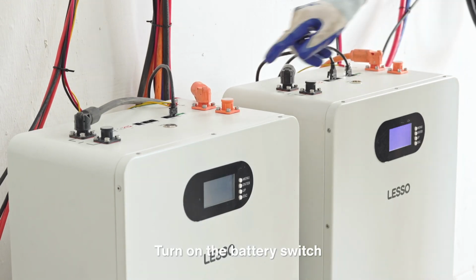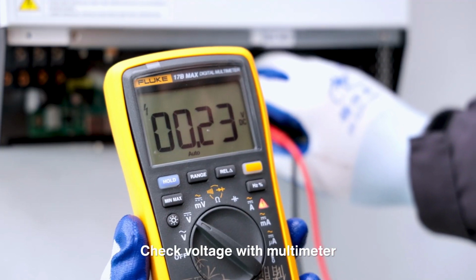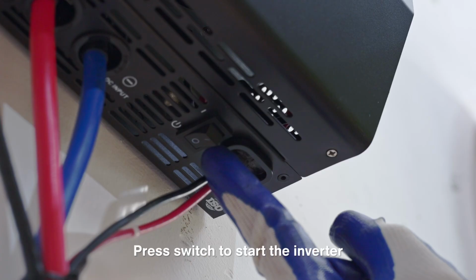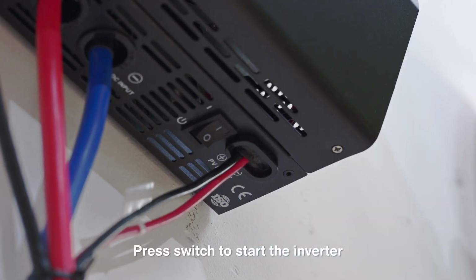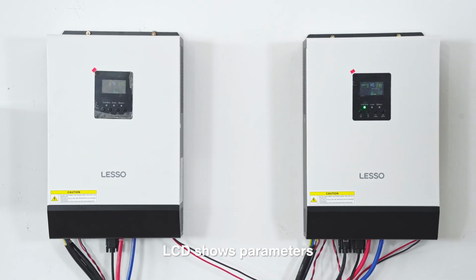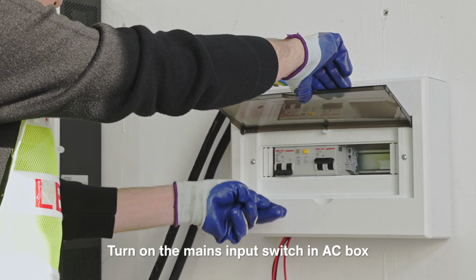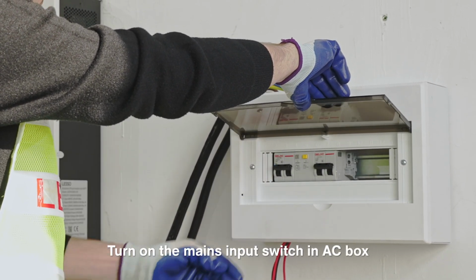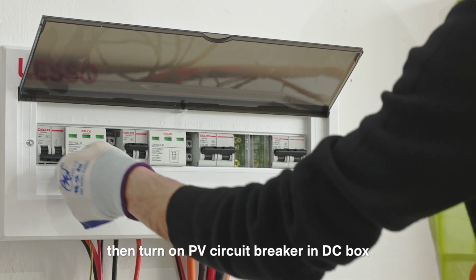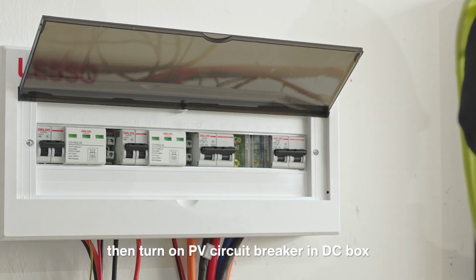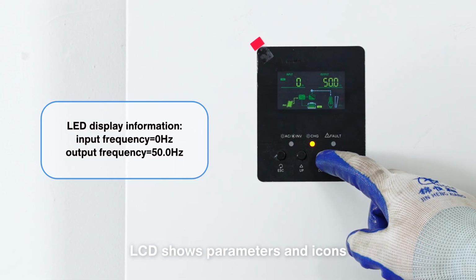System debugging. Turn on the battery switch. Check voltage with multimeter. Press switch to start the inverter. LCD shows parameters. Turn on the mains input switch in AC box. Then turn on PV circuit breaker in DC box. LCD shows parameters and icons.